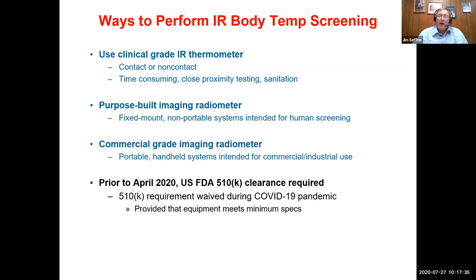Now, in order to help satisfy a need for rapid body temperature measurement, the US FDA waived the 510K requirement for the duration of the pandemic that we are currently engaged in. They waived this requirement provided that the equipment meets certain minimum specifications. And we'll talk about those on the upcoming slides.